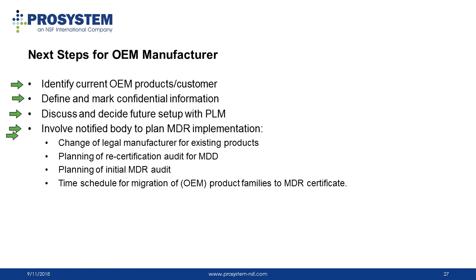You have to plan your recertification audit for the MDD in order to make sure that you've got your certifications available as long as possible. And you have to plan your MDR audit to make sure that in 2020 you are certified under MDR, and you have to schedule the migration of these product families to the MDR certificate afterwards, after 2020.